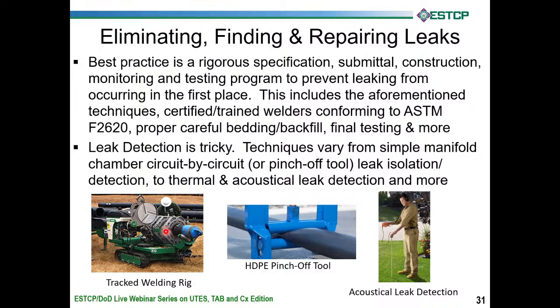Another tool that may scare you to death when you first see it is a pinch-off tool. If you're in a place where there's not a manifold chamber or a good way to valve off this, you can actually pinch off the flow to that area, work on it, and open it back up. And you think you're destroying the pipe. But in general, the manufacturers approve this protocol as long as you use the right machine. You don't apply too much pressure. Obviously, you want a nice curved surface there doing the pinching. But that allows you to isolate the piping live while you work on it.